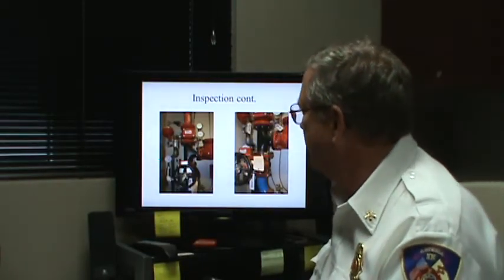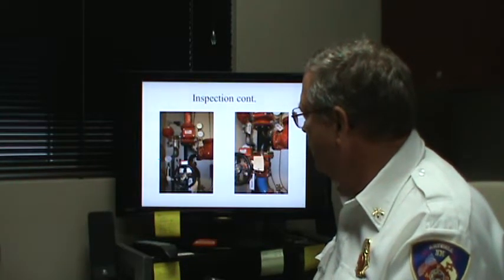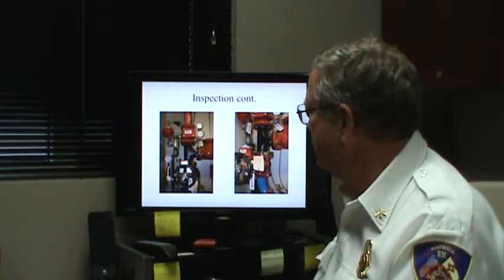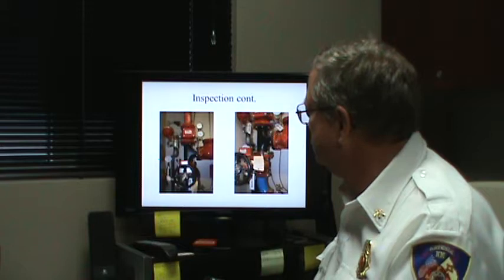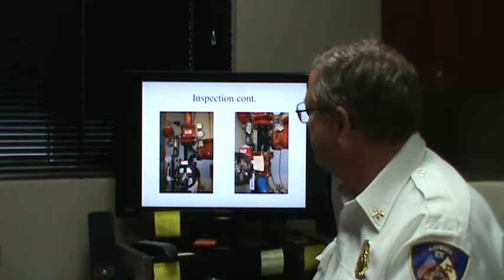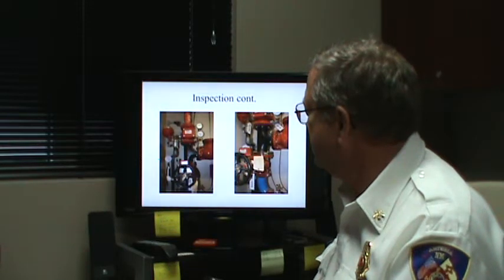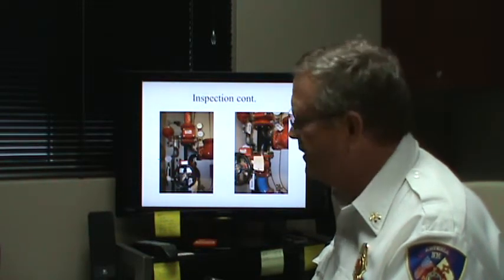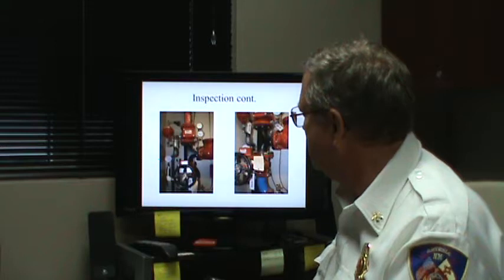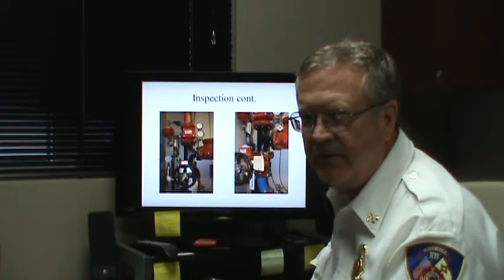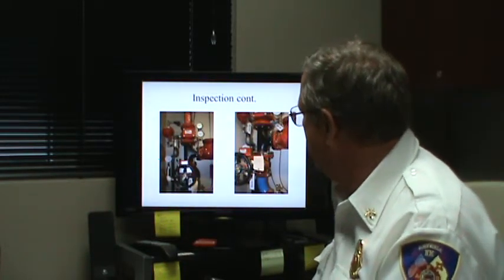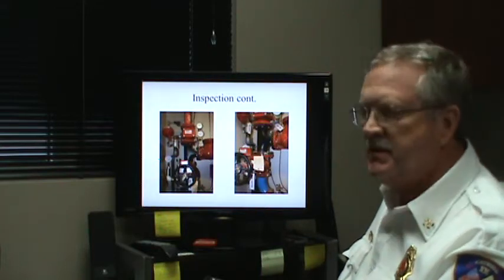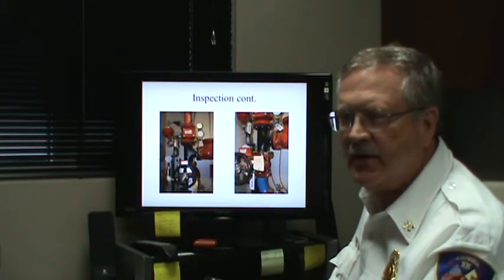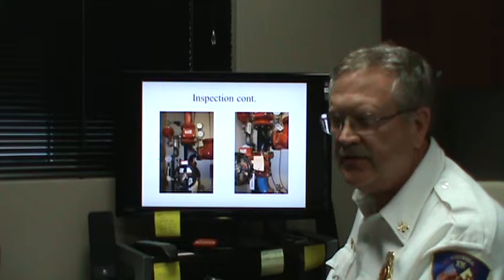All right, here's the riser, and you can see the tags are here. Our water comes in from the back part. There is a difference of about 5 pounds. I think this reads 60, and this reads 65, so it's about a 5-pound difference there. And in this picture, you can see the tag where it was inspected. It's marked July of 2013.